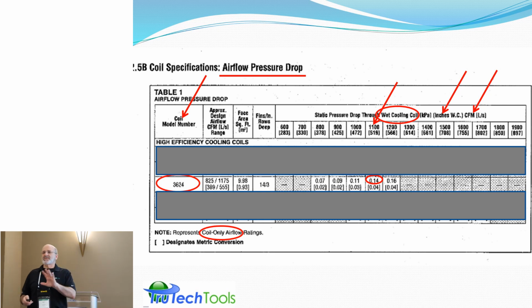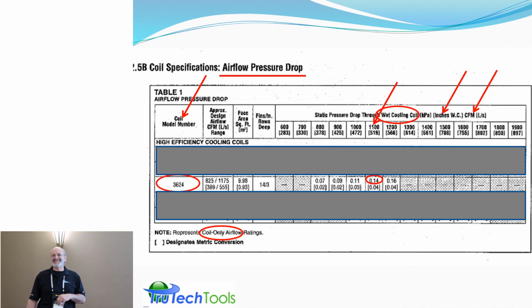How far off? Somebody's probably going to ask that. I can't tell you because it's going to vary. Do you have a number in your head? Nope. I have no numbers in my head at all. I've typically done that back and forth on drying wet coils, and I've seen about a 10%. 10%, okay, very good. That's the first time I heard someone speak up with that.